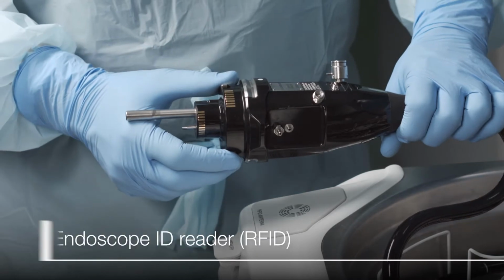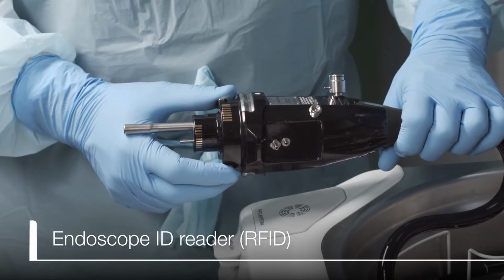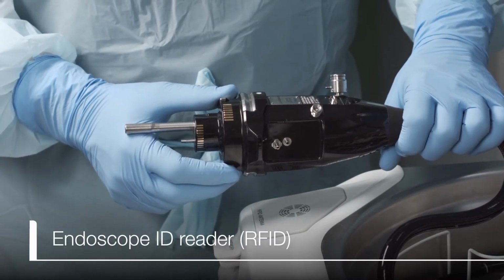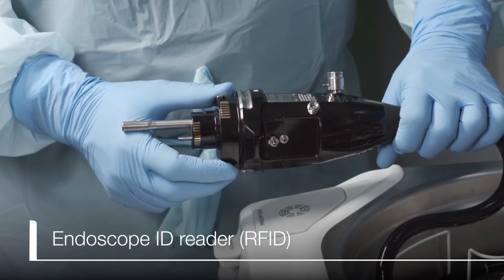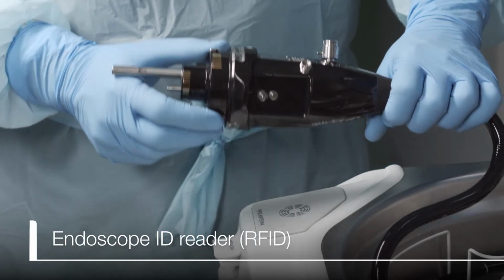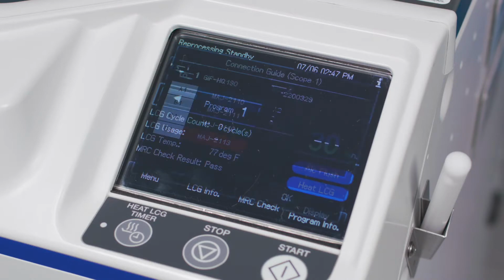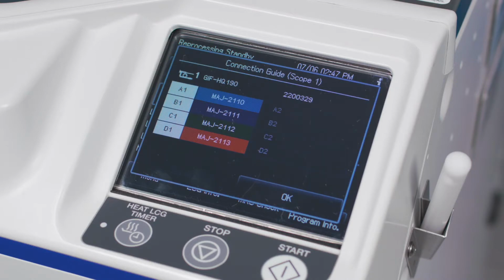Next, hold the internal ID type endoscope connector, or the external ID tag, over the ID reader section so that the reprocessor can read the endoscope information. Once the scope RFID has been scanned, the connection guide for the scanned scope will appear on the display. It's important to note that neither the ID tag nor the scope needs to touch the OER-Elite ID reader. Simply hold it parallel to the reader.